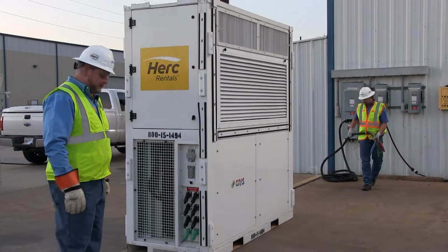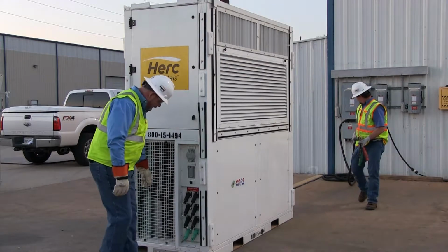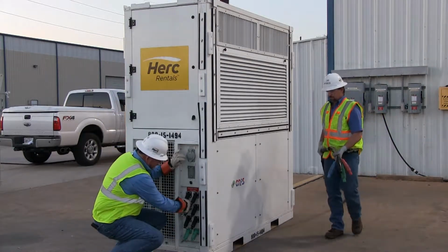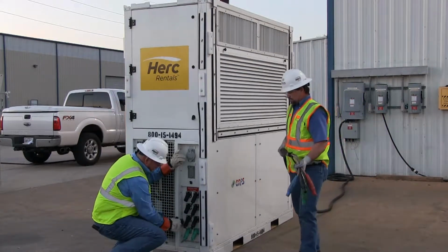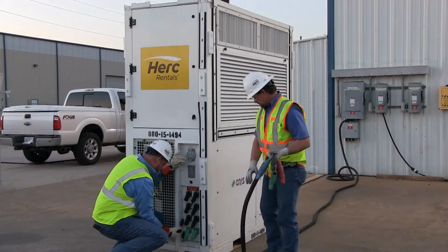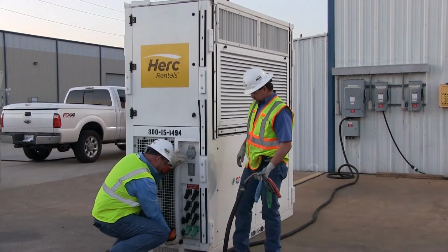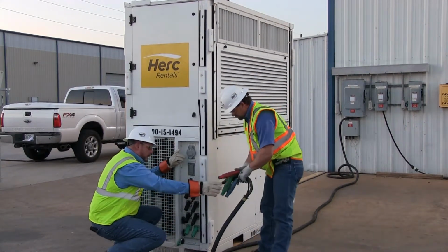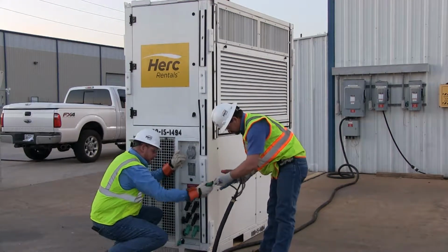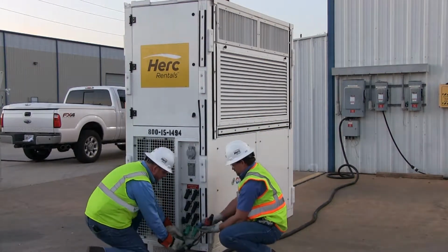Okay, the next step is to hook up the main power to the unit. Please note that we have a set of pass-through cam locks here that allows us to put two units or multiple units in series. We're going to bring in the main power leads, always connecting the ground lead first.